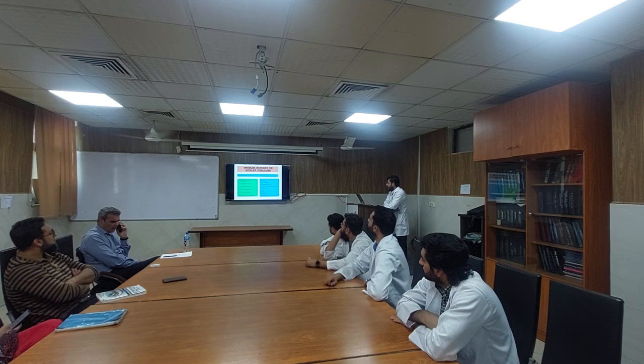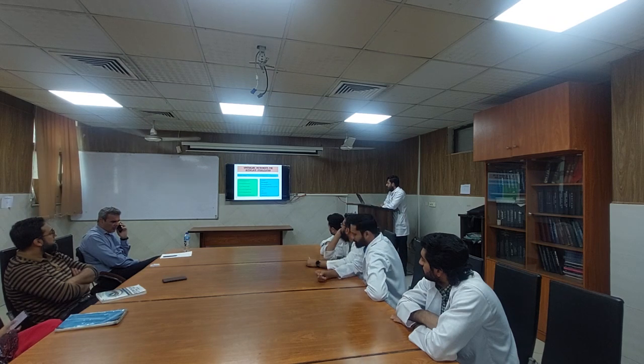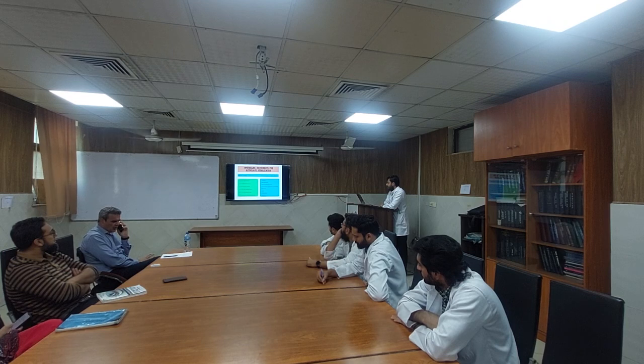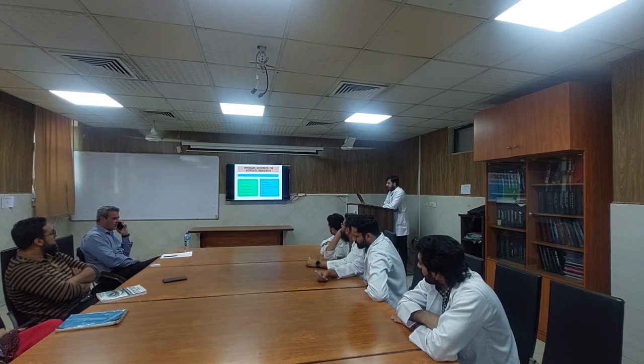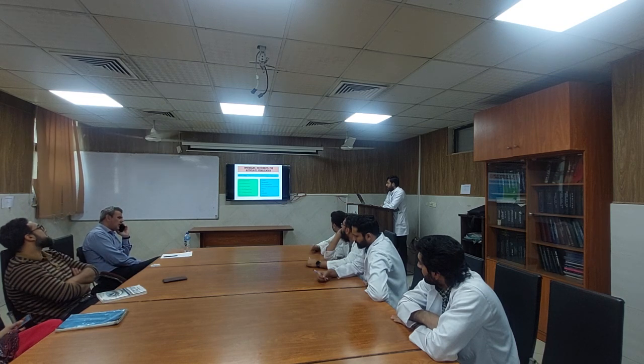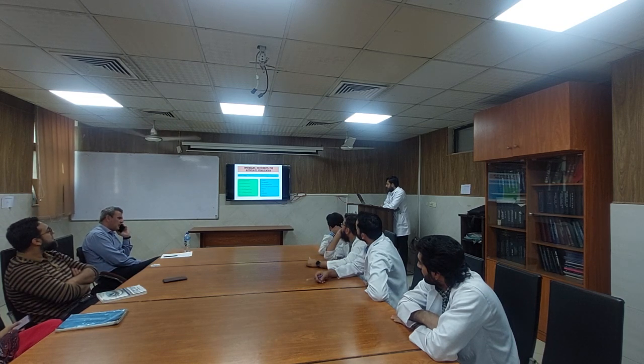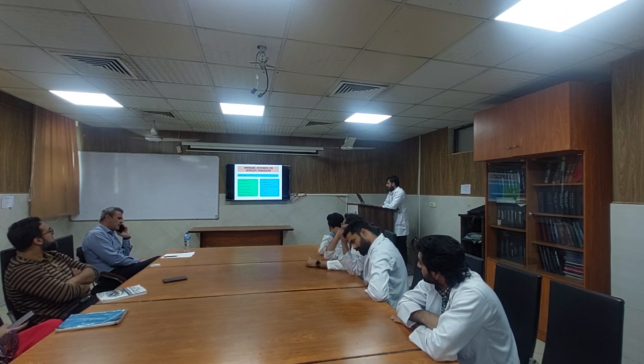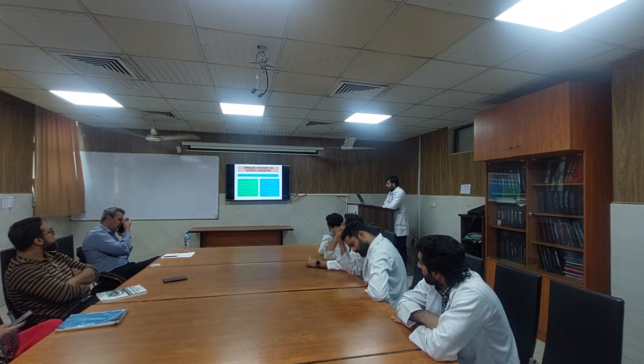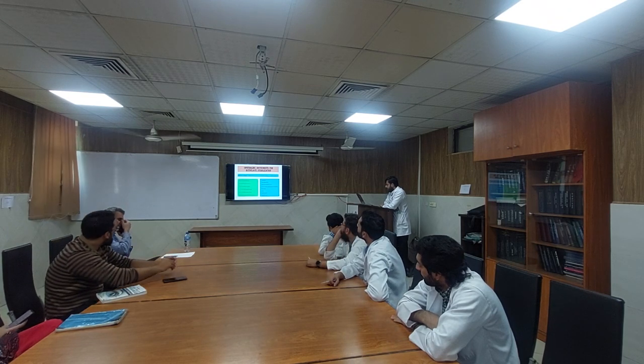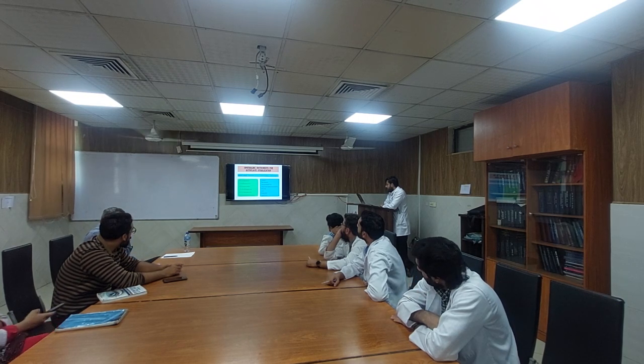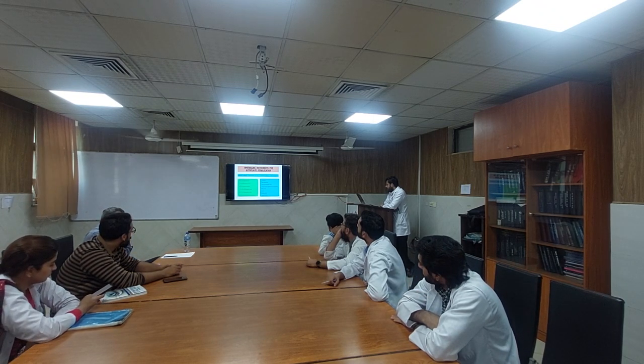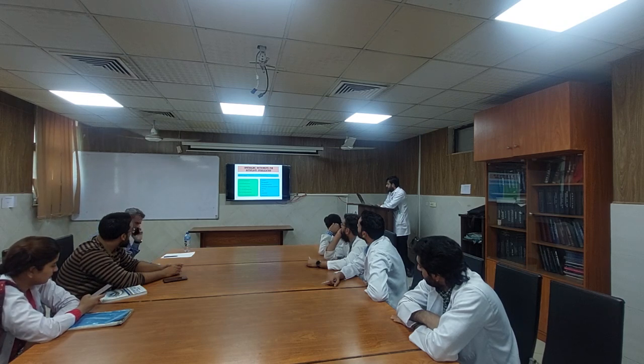Okay, here come some of the instruments which we can autoclave. As we can see, in the setting of the autoclave, to achieve 121 degrees centigrade, pressure should be 15 psi, and the instrument should be sterilized for 30 minutes. Here are some of the instruments which can be autoclaved, like 23 or 25 gauge vertical scissors, horizontal scissors, extrusion needle, ILM peeling forceps, cryoprobe, phaco handpiece, microscope handle covers, biom, IPD covers, linen, draping sheet, and surgical gowns.